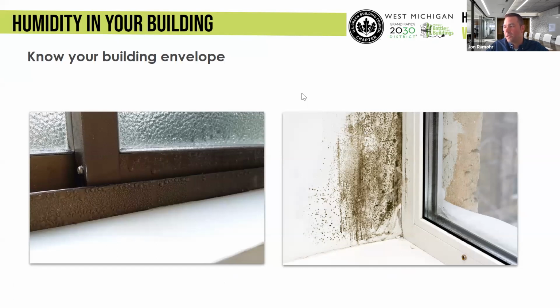So as we look at older buildings and adding humidification to them, we want to make sure we're keeping the perimeter warmer than our dew point temperature, either with perimeter heat. Many old buildings have perimeter fin tube along those exterior faces, and keeping those operational based on outside air temperature versus indoor space temperature will help guarantee that the indoor surface of the wall stays above the dew point at all times.